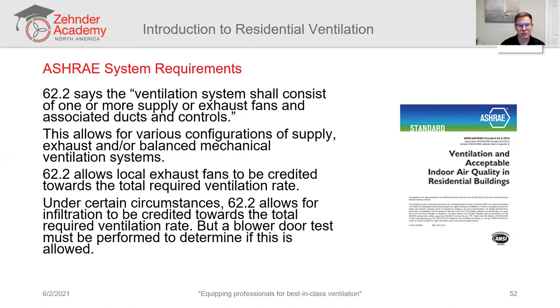Also, under certain circumstances, ASHRAE 62.2 allows for infiltration to be credited towards the total required ventilation rate, just, you know, the natural leakiness of the building. But if you're going to do that, then a blower door test has to be performed in order to quantify that leakiness or to even determine if it's at a threshold that allows it.